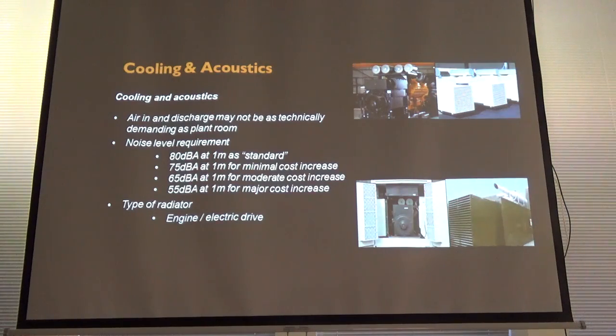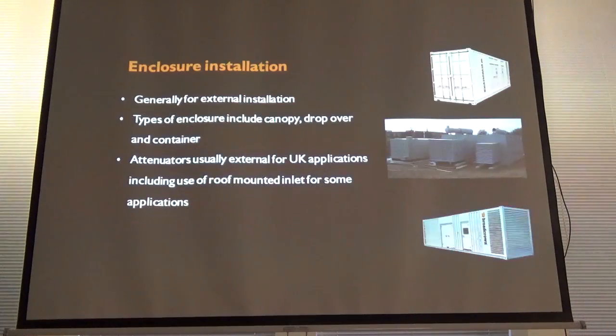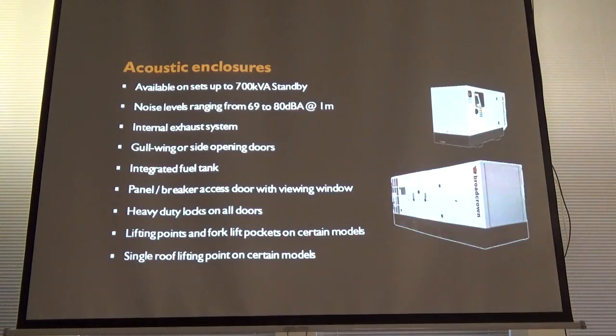Now, going back to batteries at the moment, we've got instability in the grid, we've got problems, obviously the nuclear power stations, the various connections to the continent, and the coal-fired stations being shut down. They've been producing a lot of sites where you'll have 20 megawatts of power, and it works out most cost effective with multiple 500 kilowatt units. So you've got standard enclosure units like these, big farms of them, 48, 50 units on a site, and they're splitting the emissions out. They're shoring up the grid.